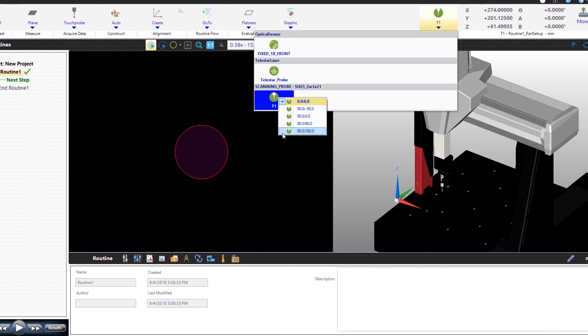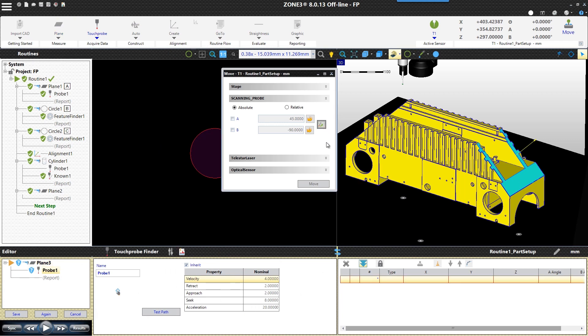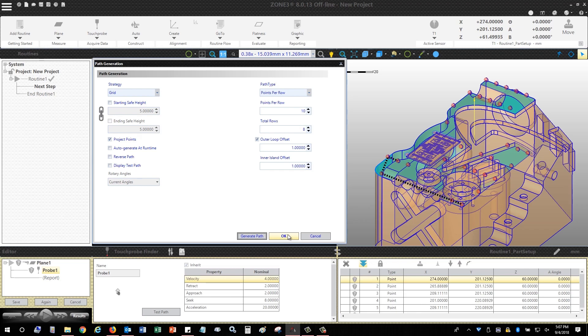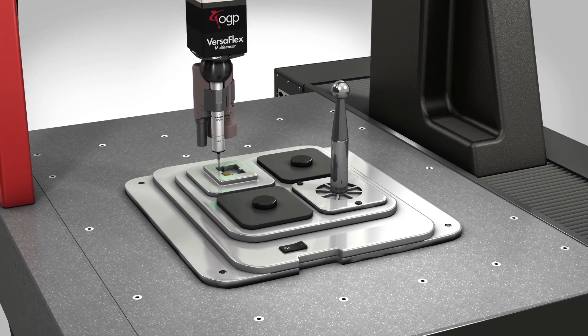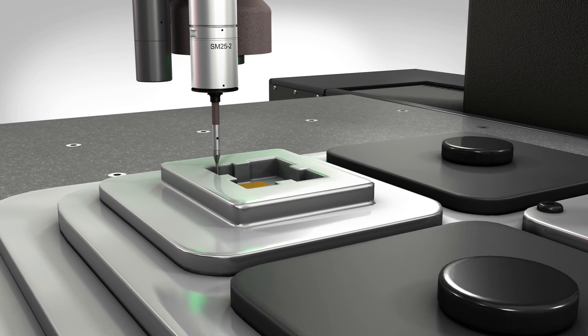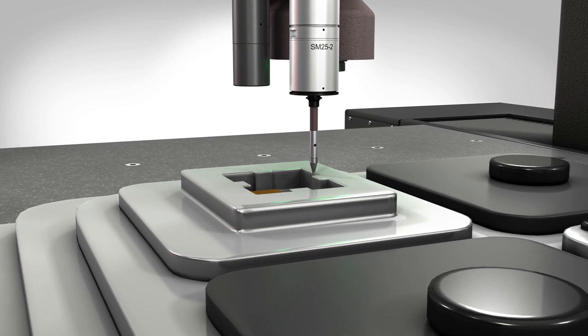User options and experiences are virtually identical regardless of which sensor is selected. Programming new parts is simple using the 3D CAD-based interface — just select the sensor and the feature and the path can be automatically generated. Calibration and verification is fully automated via the independent calibration engine. Routine sensor calibrations are fast and can be initiated with one click, and full system calibration is completely automated to minimize downtime.